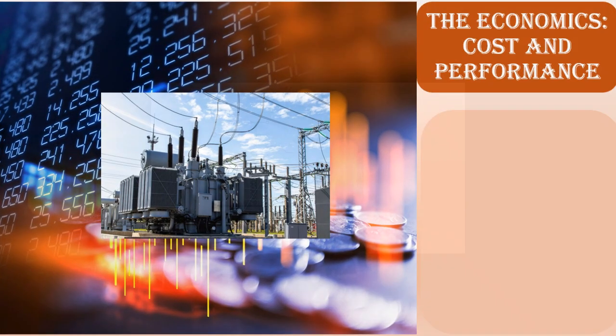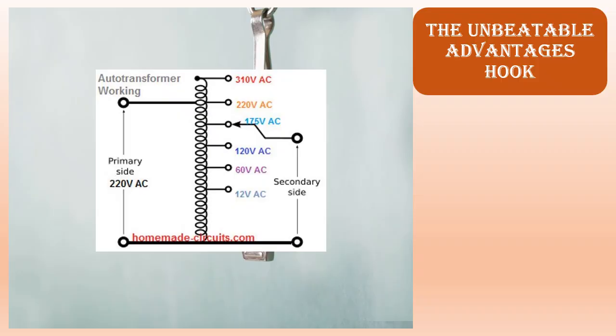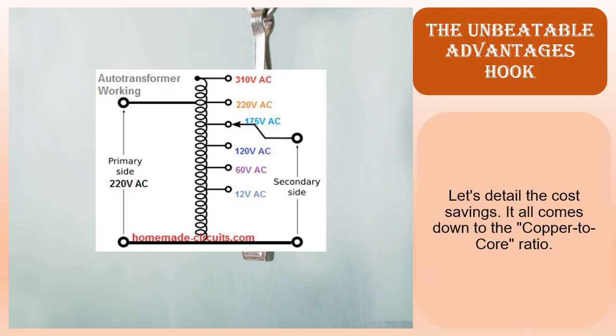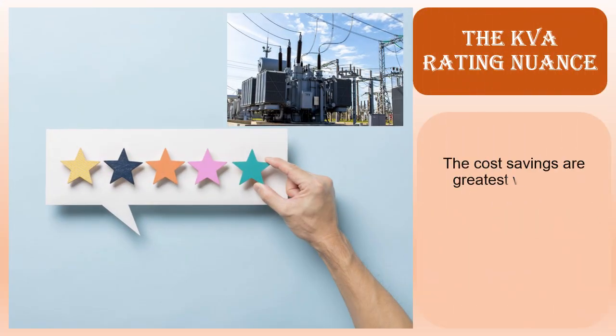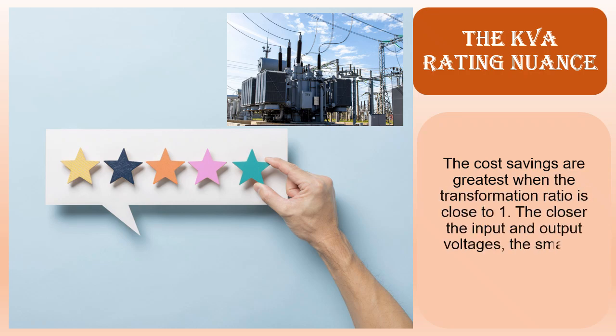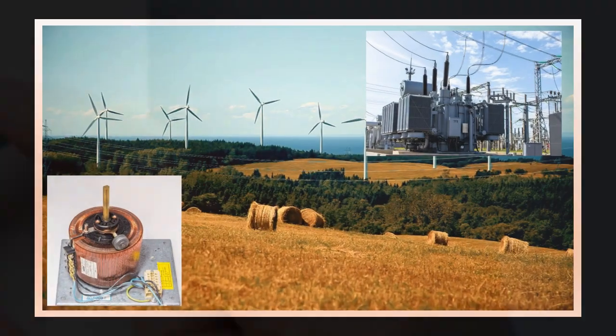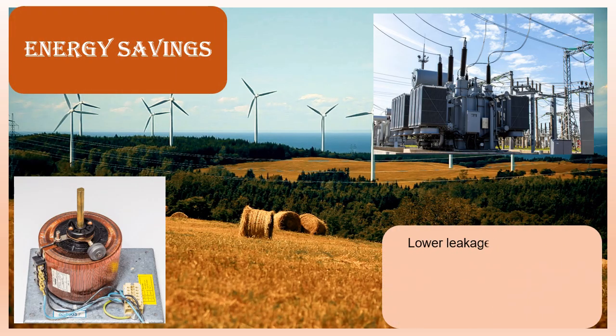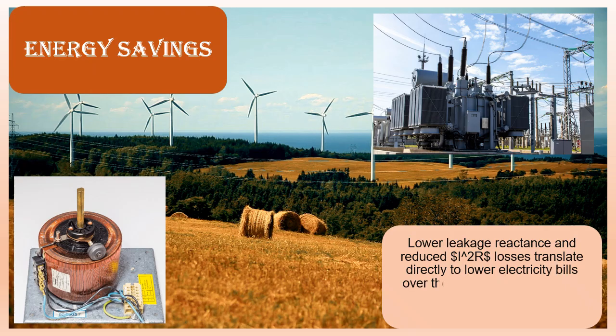Energy savings. Lower leakage reactance and reduced I²R losses translate directly to lower electricity bills over the unit's lifespan. A single percent of efficiency gain adds up quickly in continuous operations. Voltage stability. Lower impedance means the device is electrically stiff. When a heavy load engages, the voltage maintains its level with less sag, which is vital for precise electronic equipment.